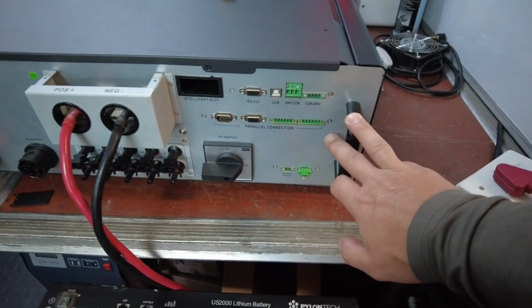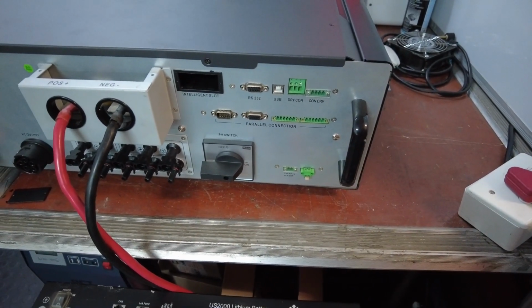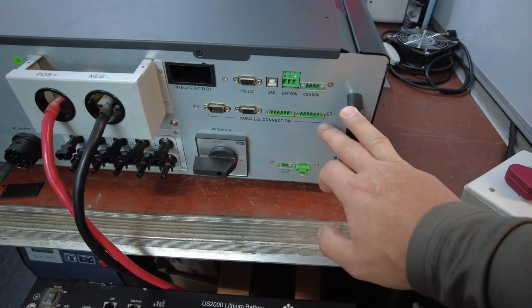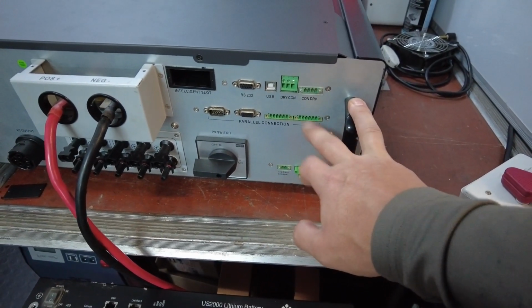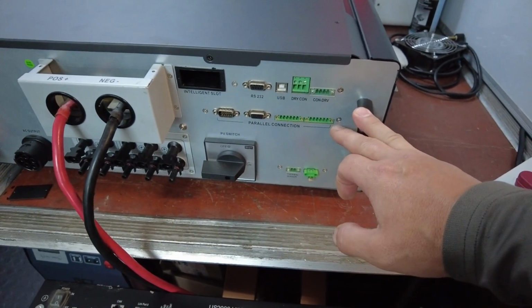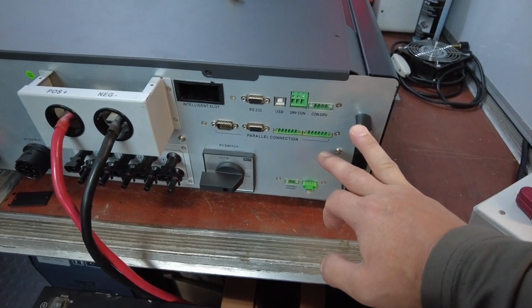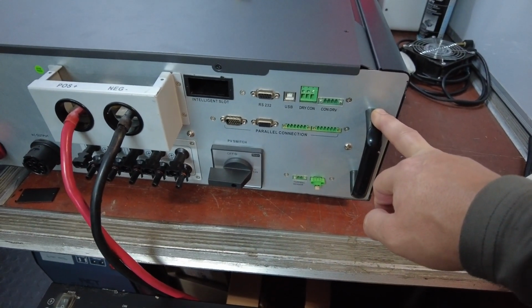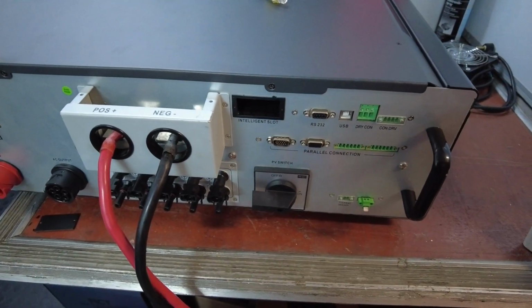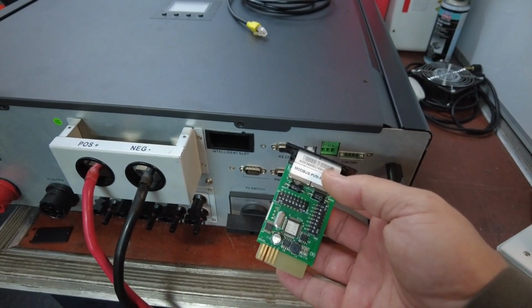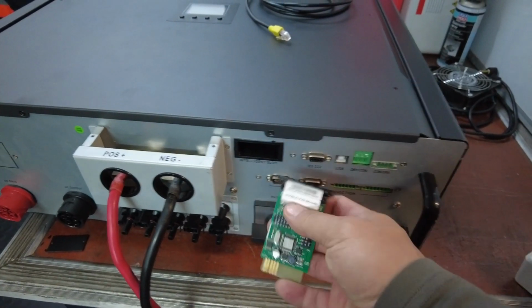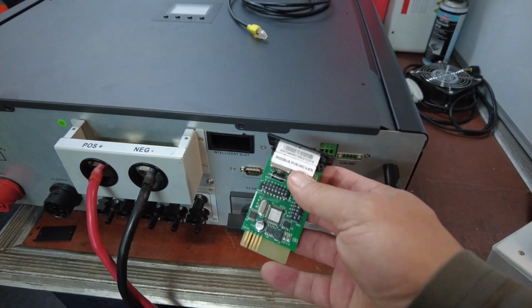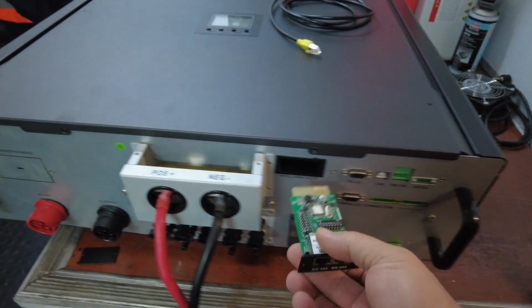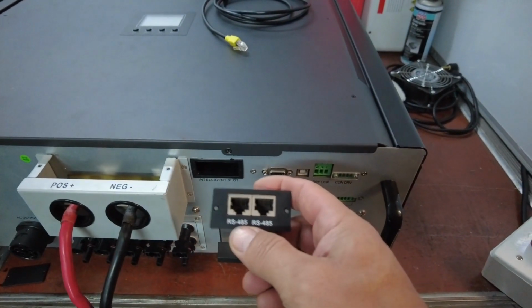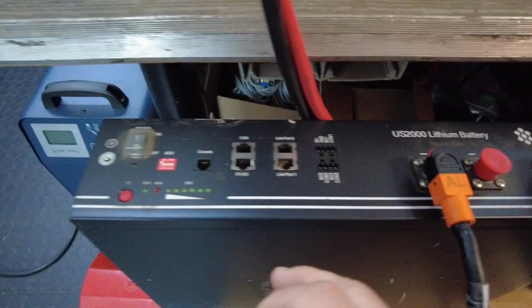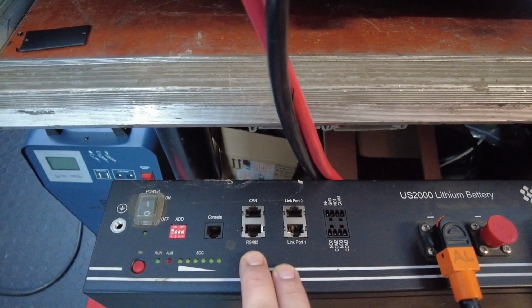So if you come to the bottom of the inverter, you will find all of the communications ports. You have your RS-232, which is for your PC, as well as your USB, your dry contacts, and then your parallel connection when you connect more than one inverter. There is no BMS port on this. However, you do have this intelligent slot. So referring to that intelligent slot, you need to actually get your hands on one of these Modbus cards, which will then slot in there, providing you with your RS-485 protocol, which will then assist you in communicating with the battery's RS-485.